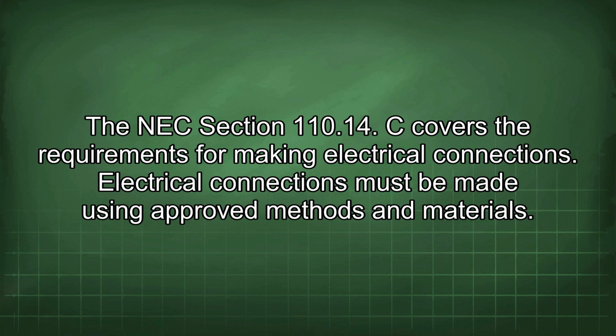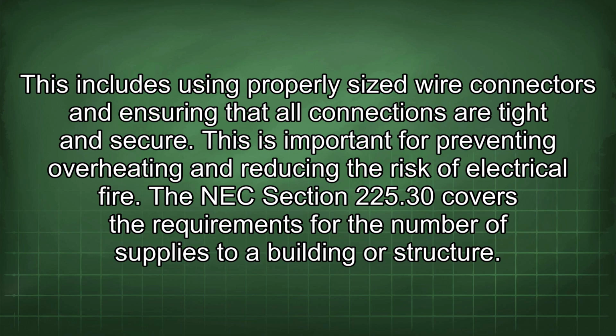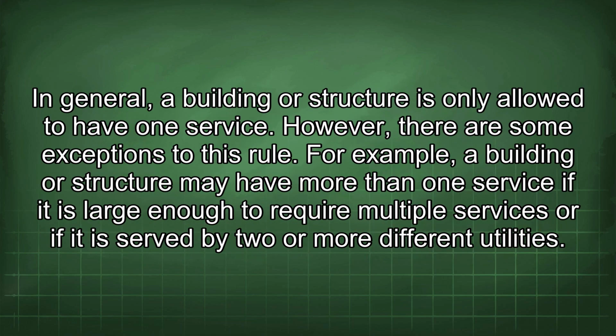The NEC Section 110.14(C) covers the requirements for making electrical connections. The electrical connections must be made using approved methods and materials. This includes using properly sized wire connectors and ensuring that all connections are tight and secure. This is important for preventing overheating and reducing the risk of electrical fire. The NEC Section 225.30 covers the requirements for the number of supplies to a building or structure. In general, a building or structure is only allowed to have one service. However, there are some exceptions to this rule.